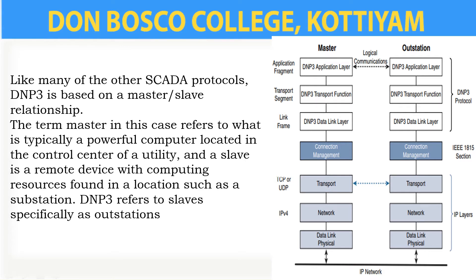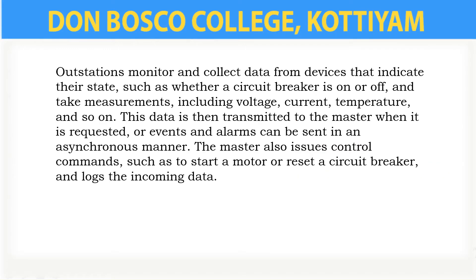Like many other SCADA protocols, DNP3 is based on a master-slave relationship. The term 'master' refers to a powerful computer located in the control center of a utility, while a 'slave' is a remote device with computing resources found in a location such as a substation. The outstations monitor and collect data from devices that indicate their state — such as whether a circuit breaker is on or off — and take measurements including voltage, current, and temperature.